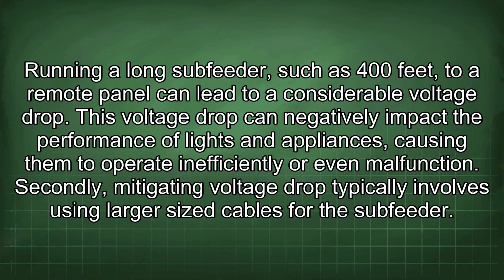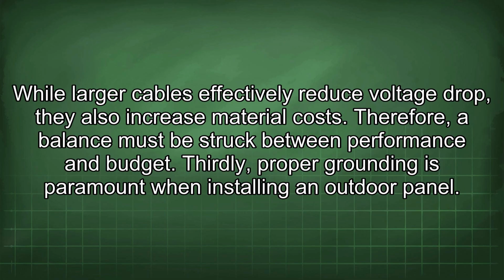Running a long subfeeder, such as 400 feet, to a remote panel can lead to a considerable voltage drop. This voltage drop can negatively impact the performance of lights and appliances, causing them to operate inefficiently or even malfunction. Secondly, mitigating voltage drop typically involves using larger size cables for the subfeeder. While larger cables effectively reduce voltage drop, they also increase material costs. Therefore, a balance must be struck between performance and budget.